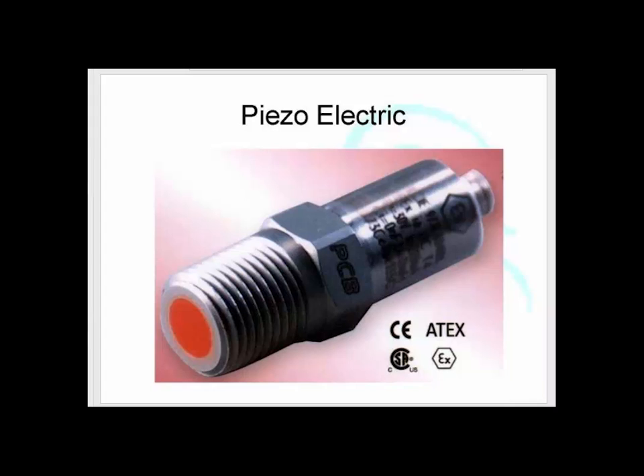The problem is, they're really great at measuring changes in pressure. With your barbecue crystal, if you keep it pushed in, you don't continually get 20,000 volts out of it - you get one lot, and then it needs resetting. It's the same with the piezoelectric pressure sensor: it's great at measuring a change, absolutely fabulous at measuring vibration. They're great for things that vibrate because they give a lovely signal out, but not very good at measuring continuous pressure because, truth be told, the only thing they actually measure is changes - they measure acceleration.